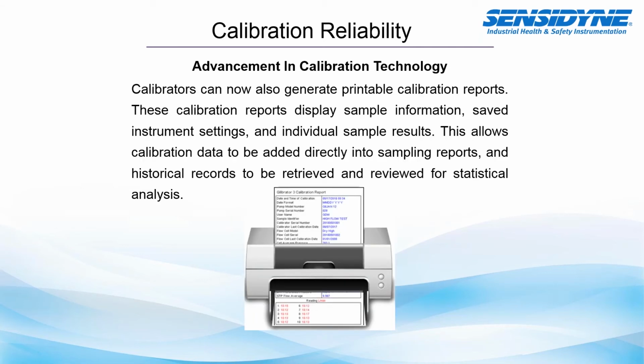Calibrators now can also generate their own printable calibration reports. The Calibrator 3 is an example of this. These calibration reports display that sample information, saved instrument settings, and individual sample results all within this calibration report. This allows the calibration data to be added directly to your sampling reports and historical records, which can be retrieved and reviewed for later statistical analysis.